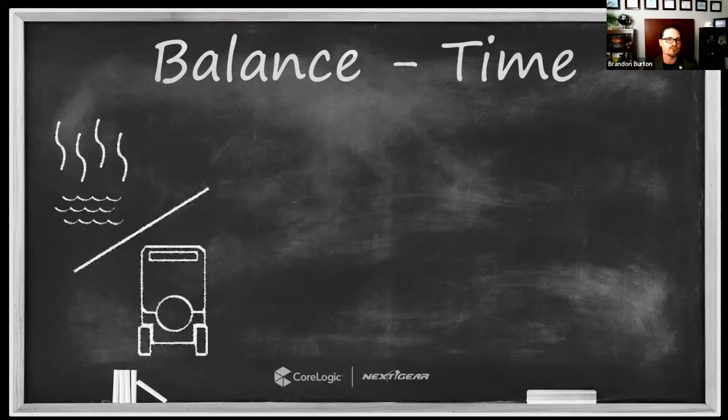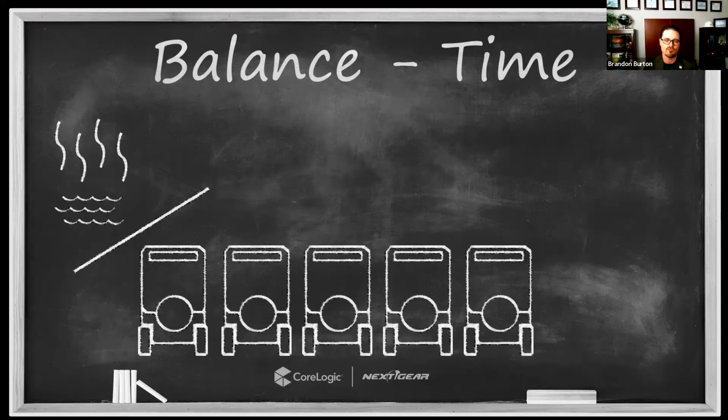Typically, the reaction that many have when they see this problem is that I must not have enough dehumidification, right? My dehumidification must be inadequate. So the knee-jerk reaction is, let's add more dehumidifiers, right? Humidity is increasing over time. Let's throw more dehumidifiers at the problem. And now we see the humidity begin to decrease over time. And then we kind of check off in our mind that we've solved the problem. In reality, however, we haven't.